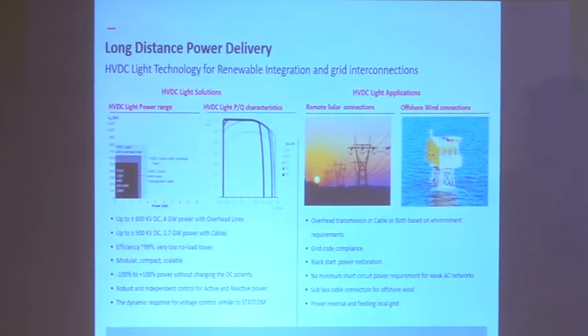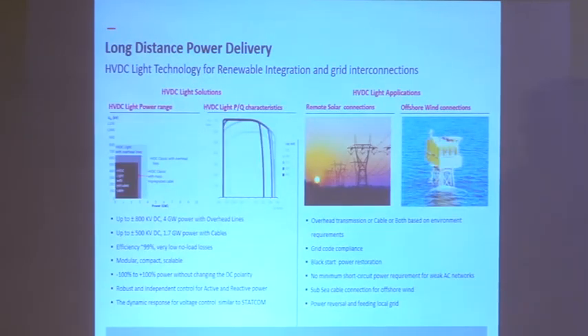VSC is a new technology of HVDC, which is scoring over and complements the growth of renewable energy. Both are helping each other in technology as well as growth. VSC has an additional benefit in HVDC, wherein it can connect with a passive load on one side and active on the other. This means it can connect an offshore grid, which has no grid on the other side, and it can connect places which have no grid on the other side. That's the best benefit of bringing renewable energy from anywhere to the grid using this technology.